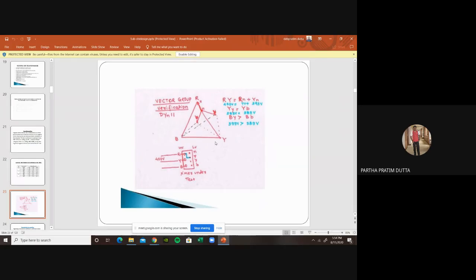If you see, 33 by 11 kV by root 3. If you see the 33 by 11 into root 3, it comes around 5.19. So whenever I use the voltage, you see the turns ratio V1 by V2 is equal to N1 by N2. So by using the turns ratio, we can check whether this transformer voltage ratio is perfect or not.